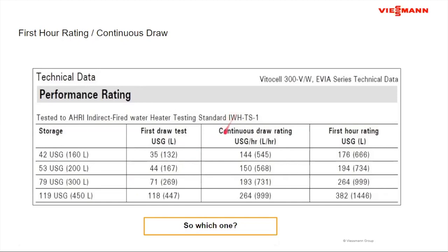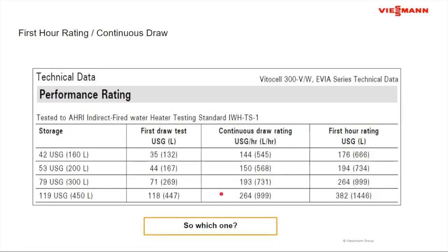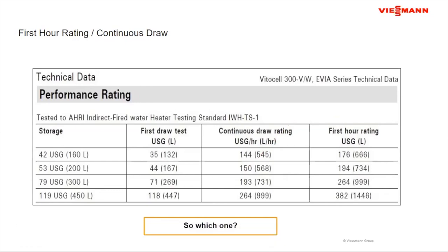And under those conditions specified by AHRI, the 42-gallon tank, I can get a continuous 144 gallons per hour through that tank. I look at the 119, that's 264 gallons per hour of continuous flow. First hour rating, as we said earlier, this is the one that I'm going to size off of residentially in most conditions. So that 42-gallon tank can give me 176 gallons of usable hot water. The 119-gallon tank, that's 382, okay?